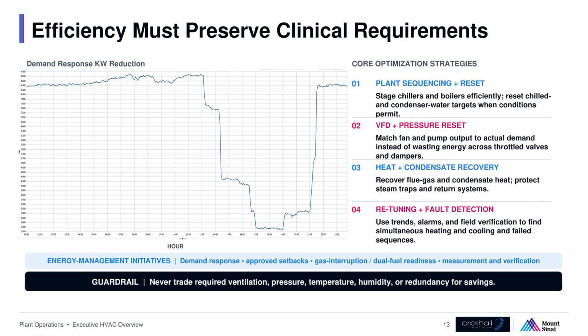We start by eliminating unnecessary runtime. Approved setbacks can widen temperature bands or reduce airflow and equipment schedules in offices and other non-critical areas when they are unoccupied. Those setbacks are never applied blindly to operating rooms, isolation rooms, labs. We then reset set points based on actual demand, chilled water temperature, condenser water targets, supply air temperature, duct static pressure, and hydronic differential pressure.